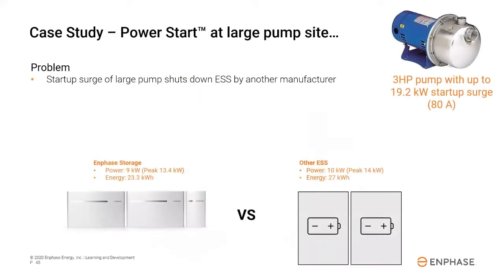Here we have a case study which illustrates the benefit of power start technology. A customer had a popular storage system from another company with 2 of their storage units. They had a large pump with a very high demand spike, and this proved to be too much for the system to handle, and the microgrid would collapse every single time the pump attempted to start. Now, why did this happen? The pump startup surge was 19 kilowatts, but the battery peak power was only 14 kilowatts. The peak power wasn't even close to enough to handle the startup surge of the pump.